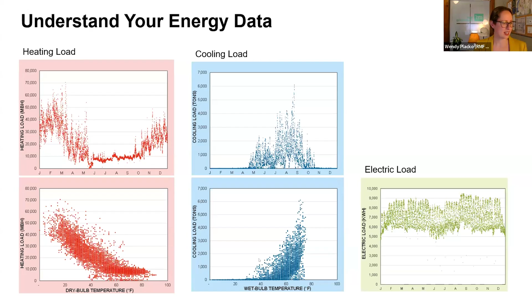One of the things we do is look at this profile, and we're not really looking at heating and cooling as separate systems - we look at them together, and how those heating and cooling loads balance each other. Do you have cooling throughout the year, or only in the summer? Likewise, do you have heating loads throughout the year, or substantial summer heating? If you have winter cooling and summer heating, it opens up some doors, which we'll get into more when we talk about low temperature hot water technologies. With steam, it's a little less of a factor, but it's something we always look for, and the technologies we recommend will be based upon that.